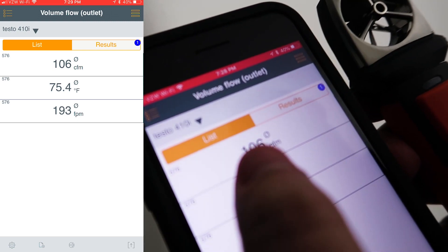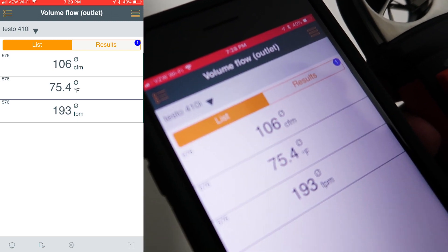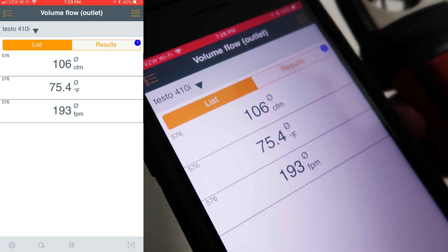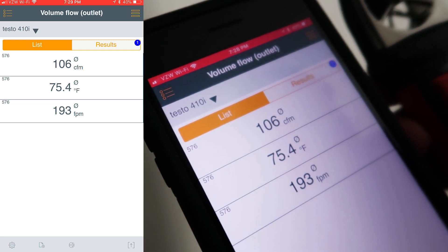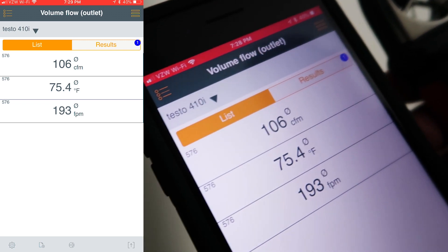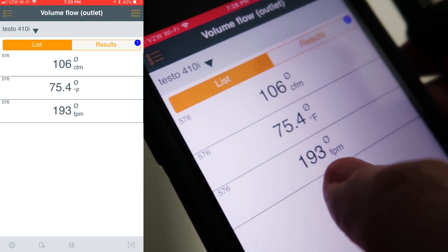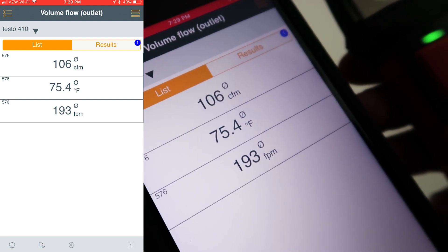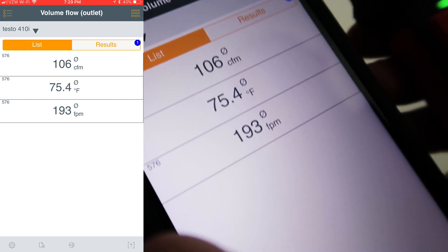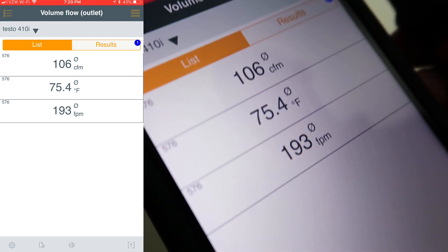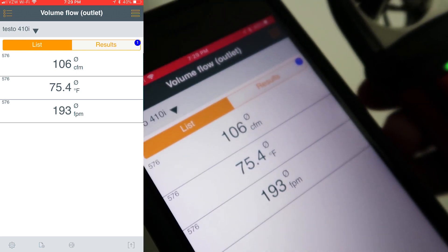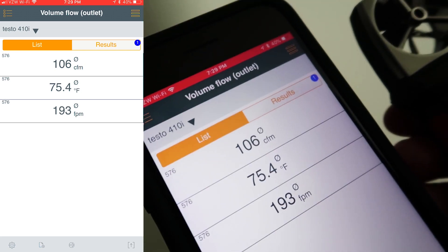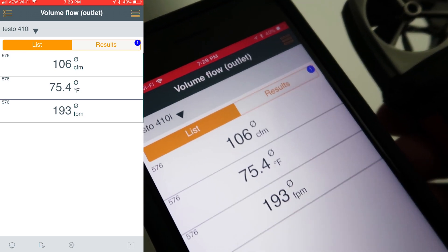You can see here that we have an average of 106 CFM. But again, in order to get that, you would have to know quite a bit about your vent. We do know that my average velocity is 193 feet per minute — that's pretty low. In this case, I know that I oversized the duct, but in many cases it would result in not having enough throw.